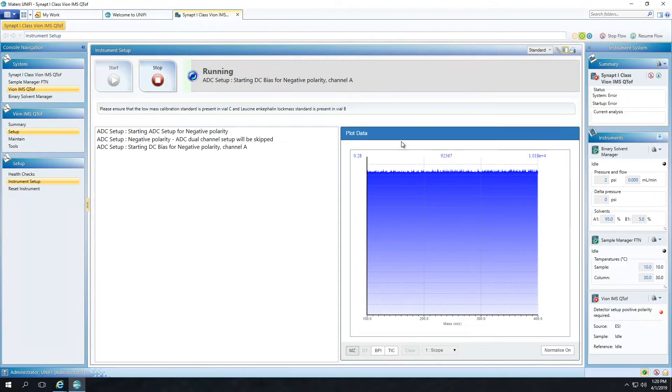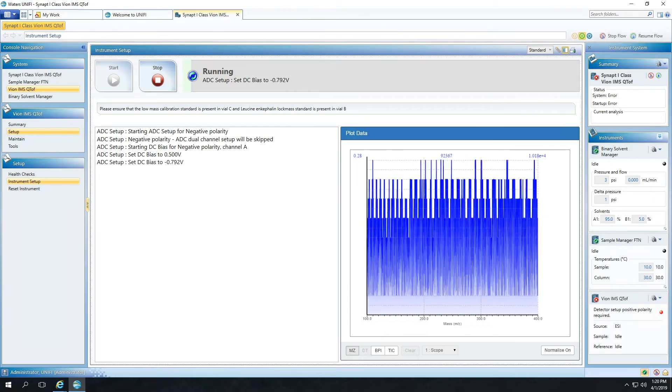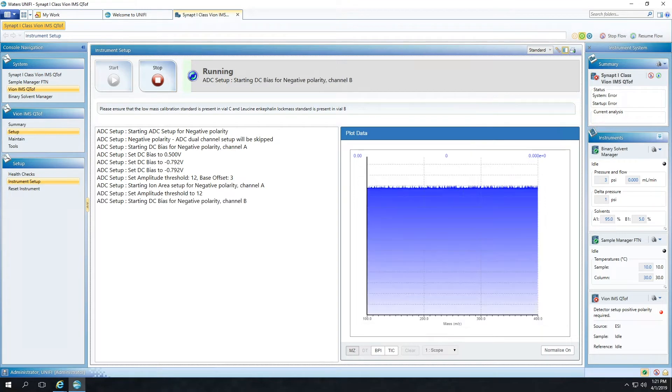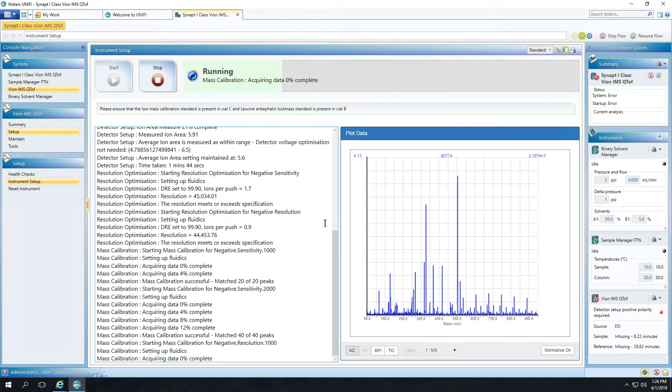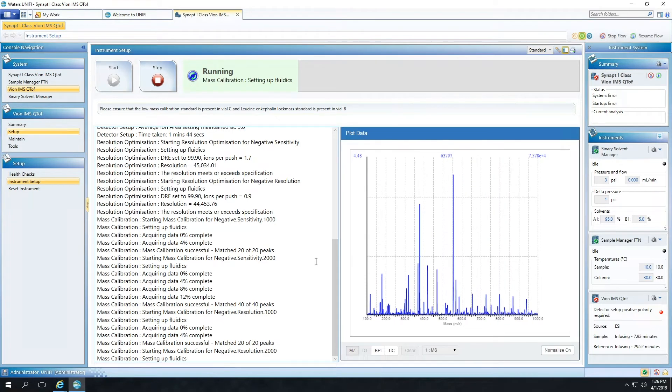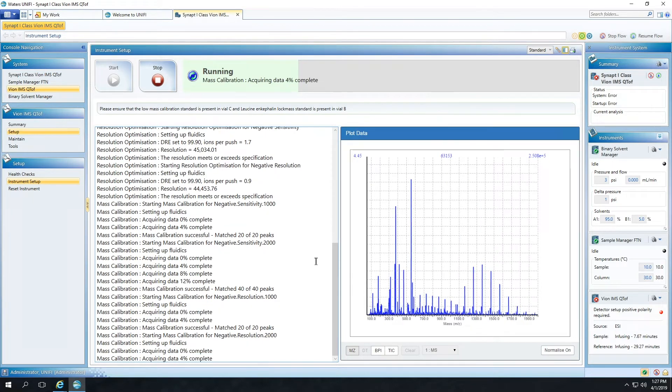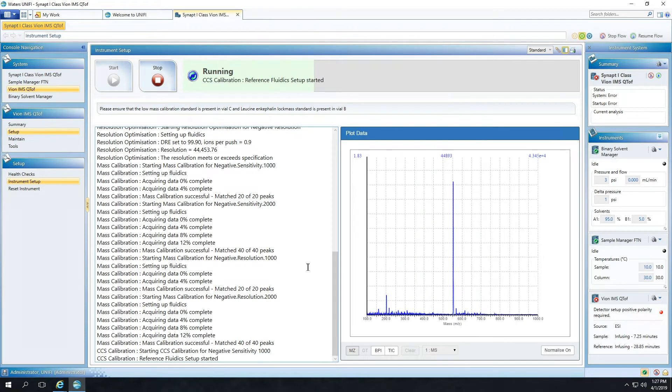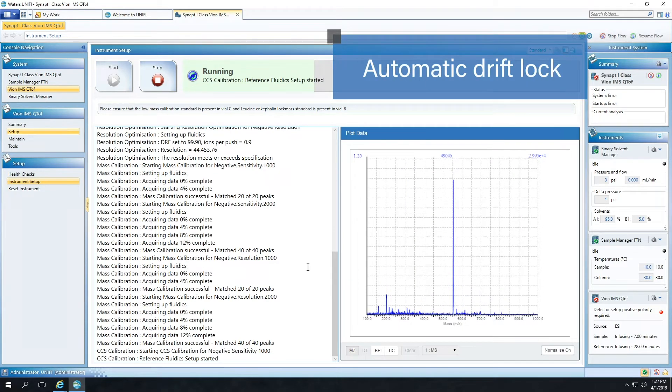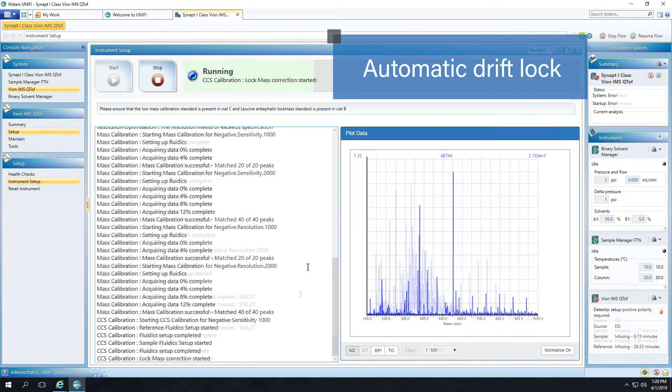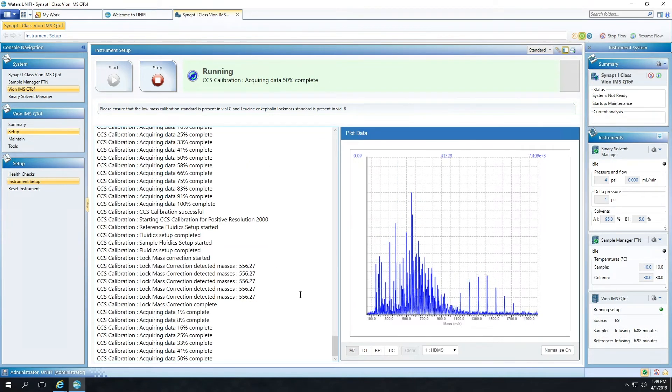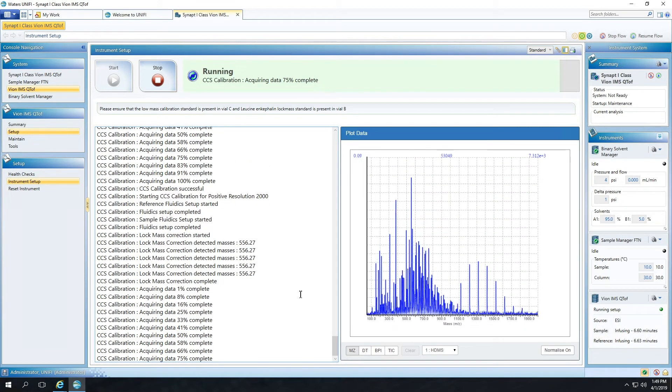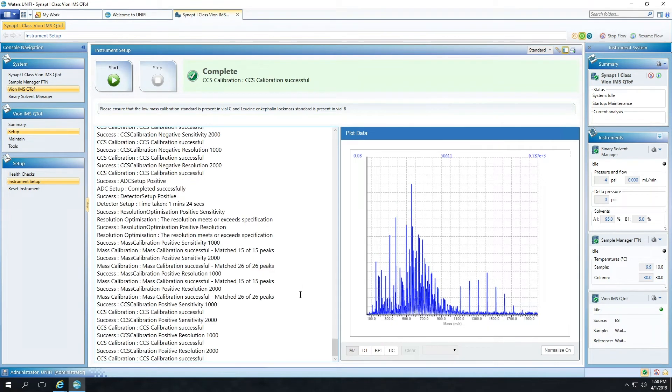Vion and UniFi also make calibrations easier and automatic. In the past, users were forced to run separate and frequent calibrations in order to generate both high quality MS and ion mobility data. With Vion, we've integrated this into a more routine, one-click, one-solution approach to automatically calibrate all the modes that a user needs. For routine use, we've also added automatic drift lock capabilities, which allows the ion mobility cell to run with better accuracy in between calibrations and generate the most consistent data possible.